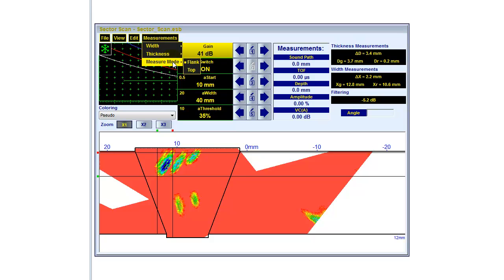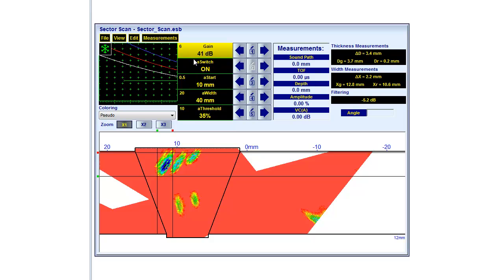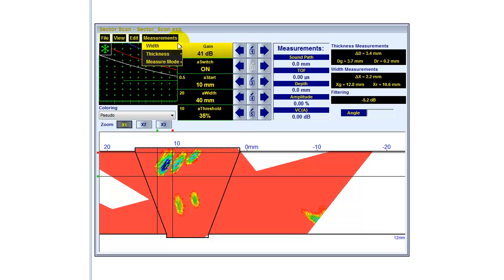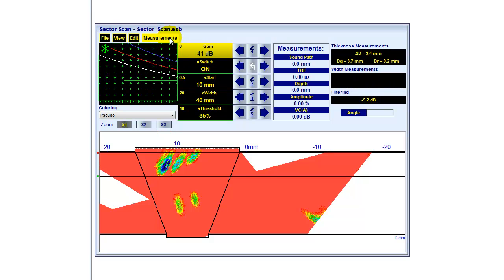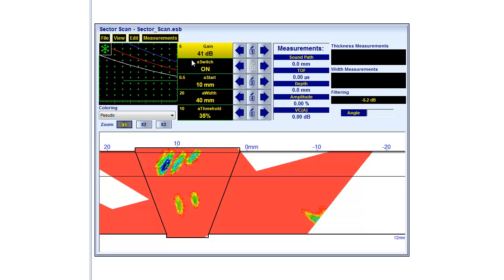Measurement mode can either be flank or top. Top means peak. And in this case, we are using flank evaluation. I want to switch those measurement values off.